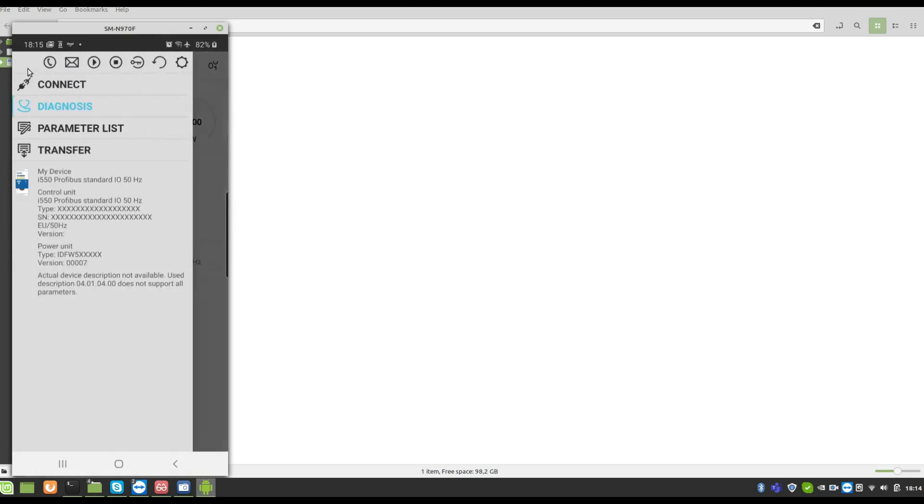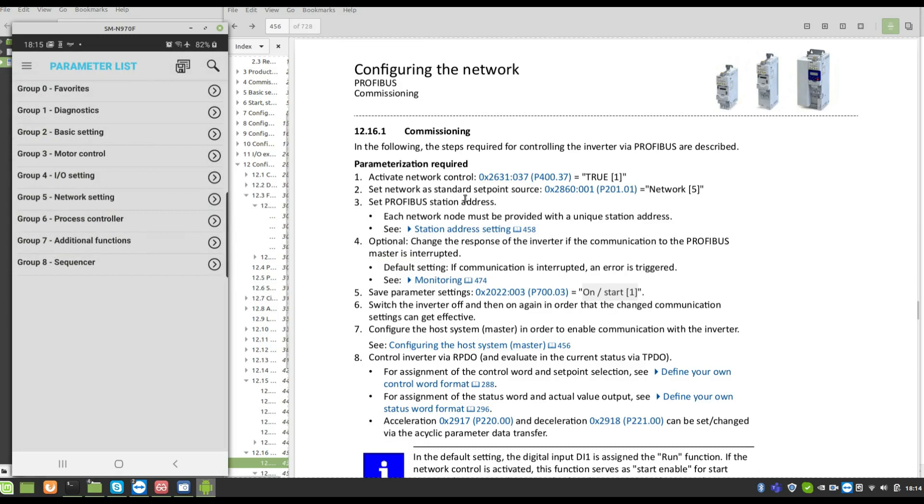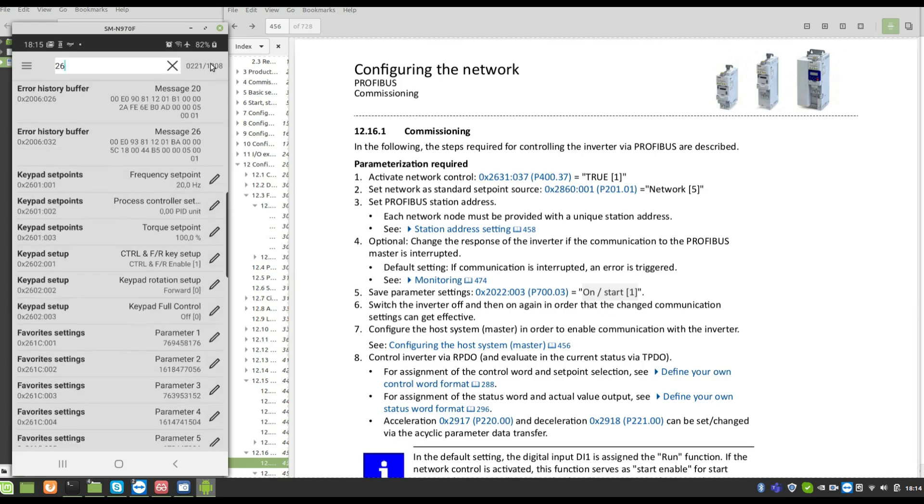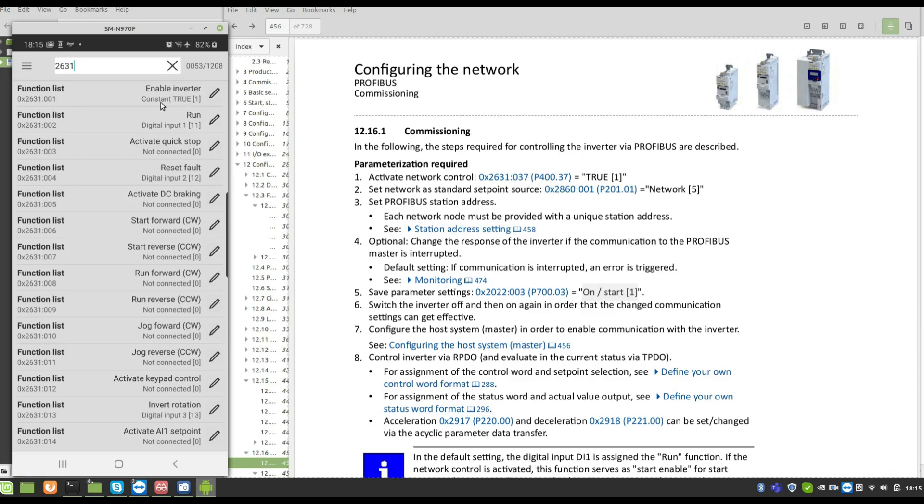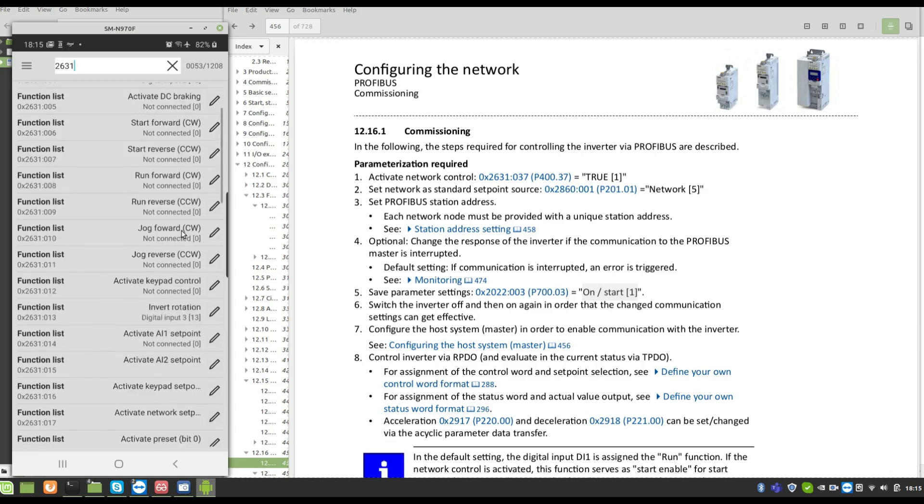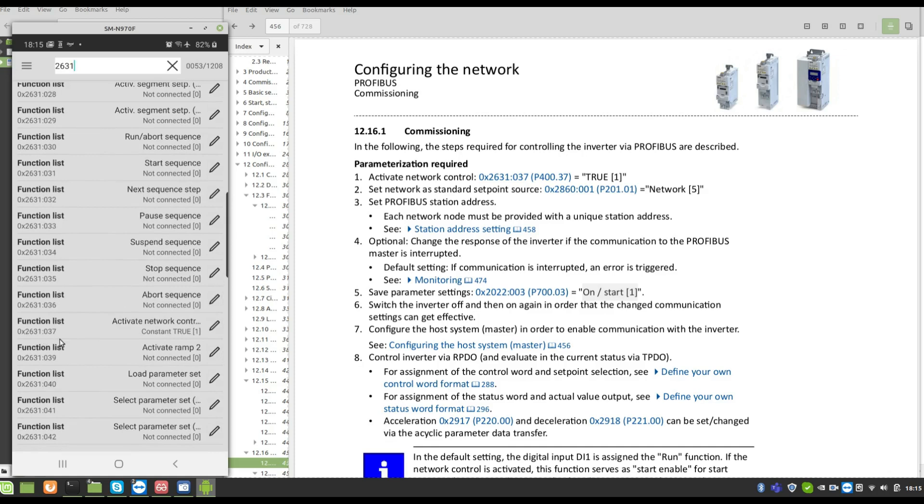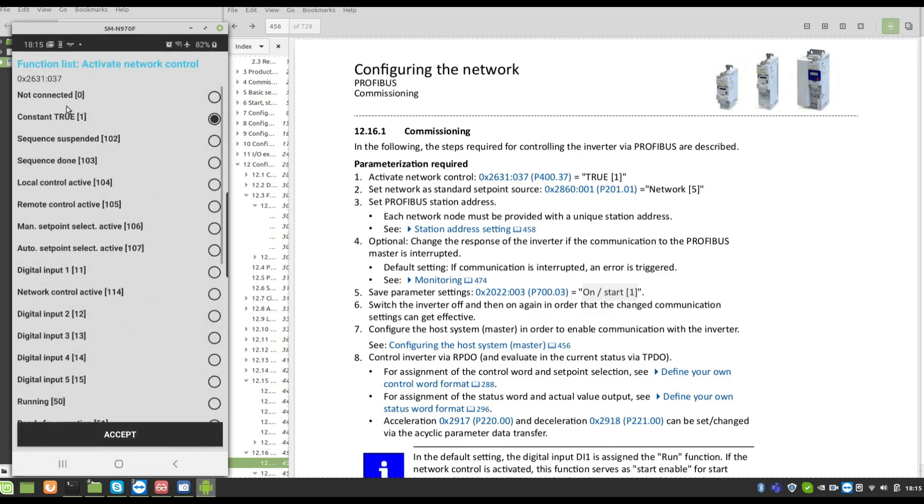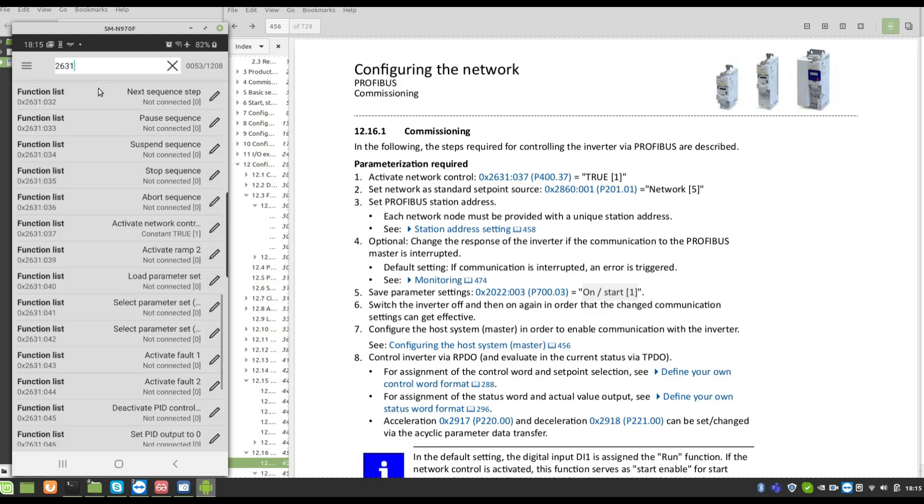I can make the parameterization now. I can set the parameters P400 sub-index 37, 2631. You must use this one when you are using the configuration card via Wi-Fi. Enable inverter, 37. Take a look, constant, true. Next parameter, set, next parameter.